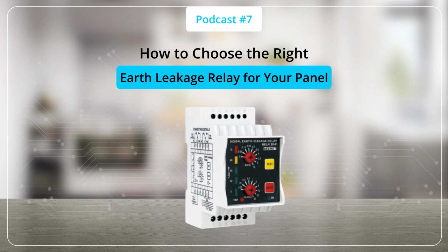While selecting an ELR, it is also important to avoid common mistakes that can compromise protection performance. One common mistake is using an undersized CBCT. This can create measurement issues and lead to unnecessary tripping. Another mistake is using an AC relay in systems where DC leakage may be present, such as installations with VFDs or electric vehicle charging systems. Incorrect time delay settings can also create problems. Delays that are too short may result in nuisance tripping, while delays that are too long can reduce protection effectiveness.